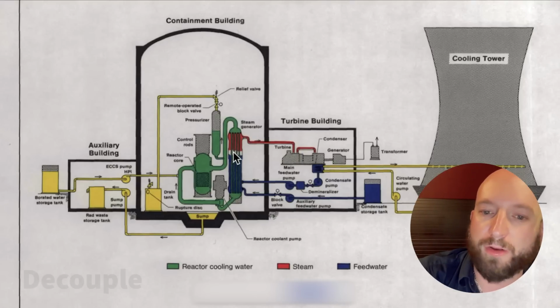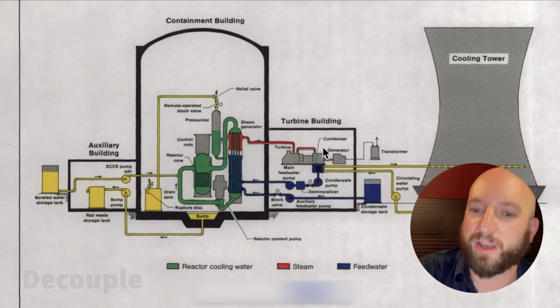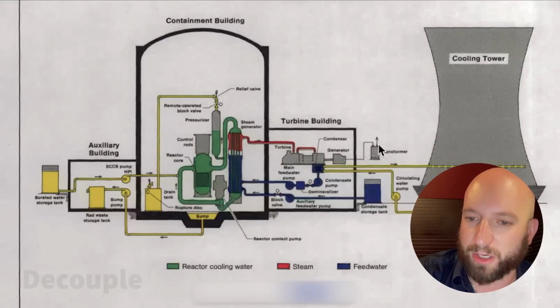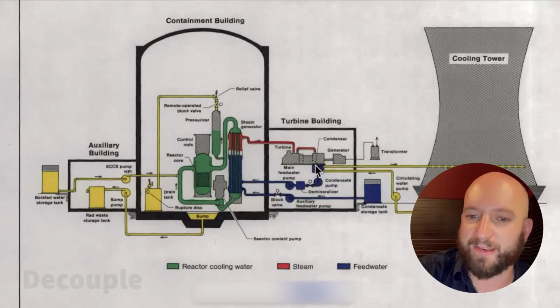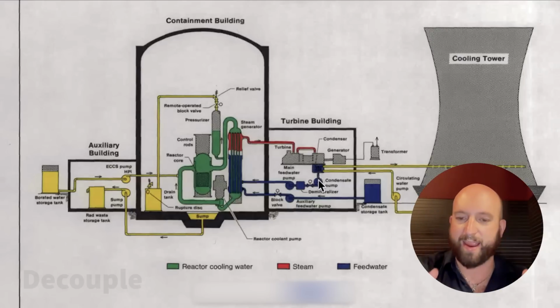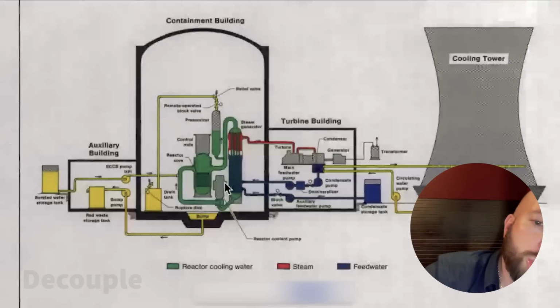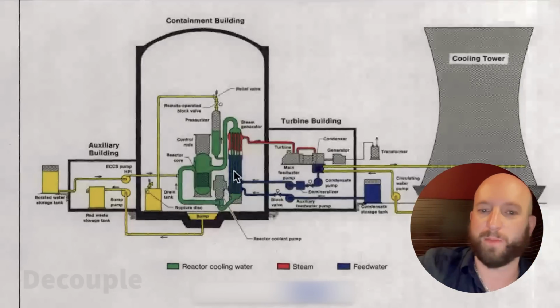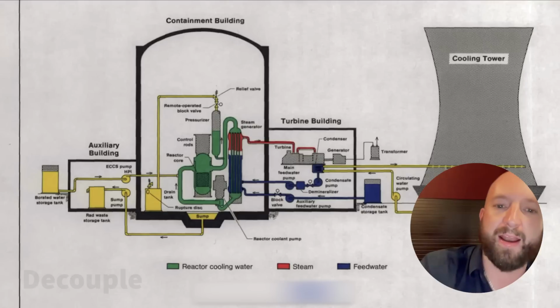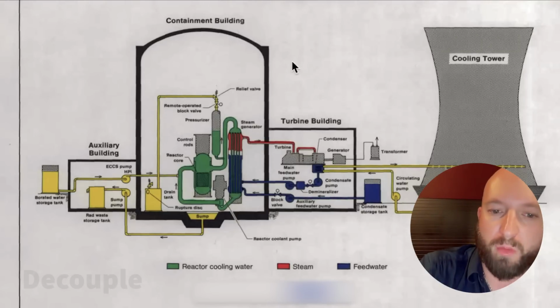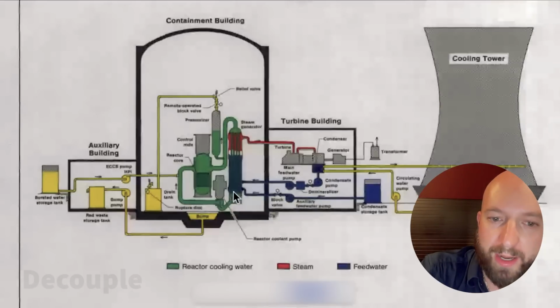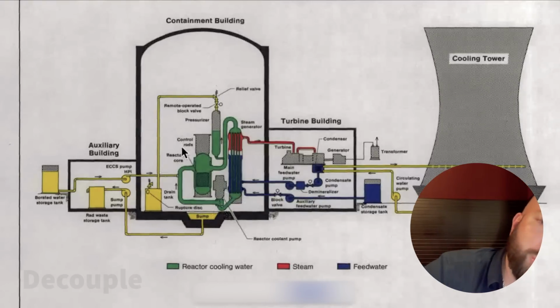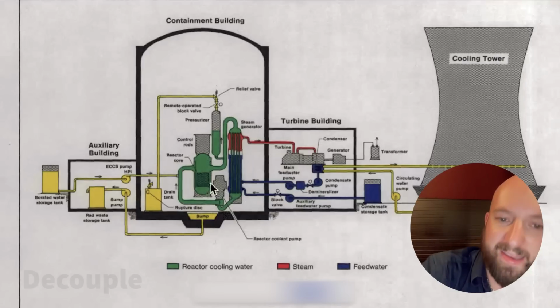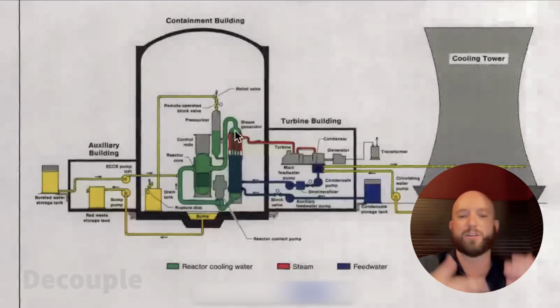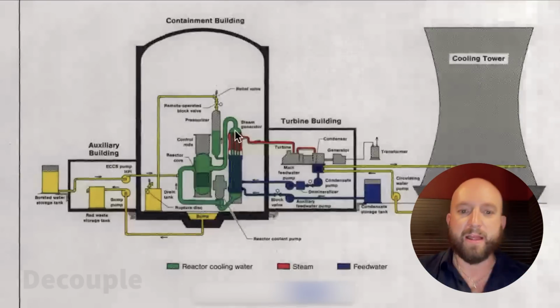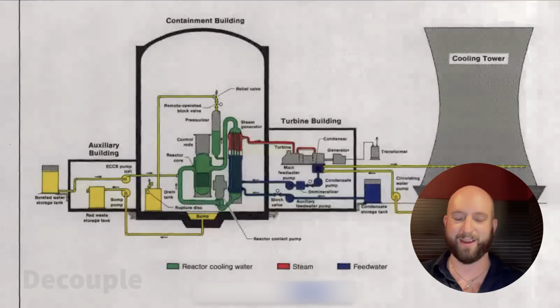So that steam then goes into the turbine, expands in the turbine, which spins the turbine, goes to the generator, turns the transformer, and that steam gets condensed by water. Then that condensate that comes out of the condenser gets pumped back to the steam generator to be boiled again, to be turned into steam. On the reactor coolant side, that water is dropping in temperature as it boils the feed water, and that cooler liquid reactor coolant gets spun by the reactor coolant pump, gets pumped through the reactor core again, gets heated up again, and goes to the top of the steam generator to boil that water. So that's a nice little circuit that we have going here.